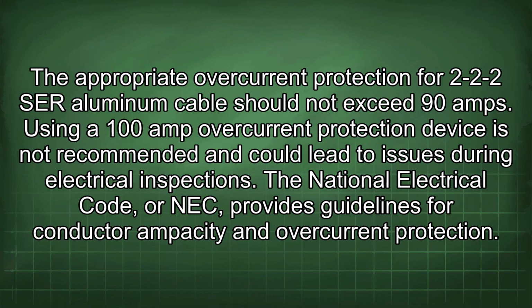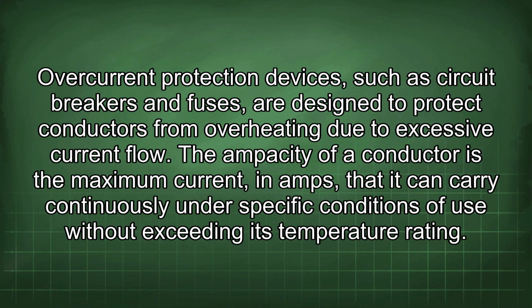The appropriate overcurrent protection for 2-2-2 SER aluminum cable should not exceed 90 amps. Using a 100 amp overcurrent protection device is not recommended and could lead to issues during electrical inspections. The National Electrical Code, or NEC, provides guidelines for conductor ampacity and overcurrent protection.